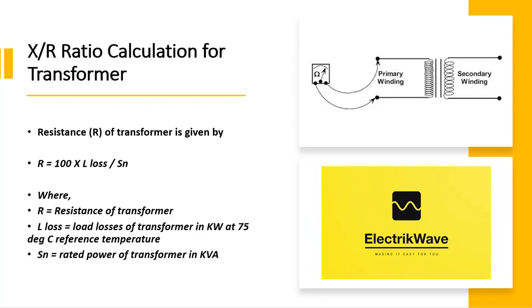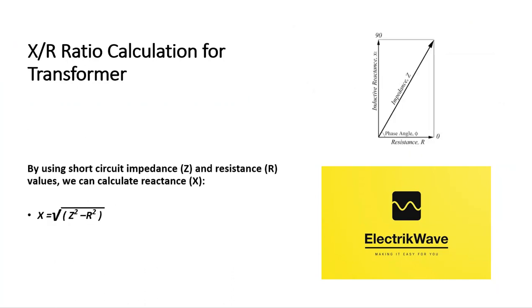Resistance R of the transformer is given by the formula, where R equals resistance of transformer, L_loss equals load losses of transformer in kW at 75 degrees Celsius reference temperature, and Sn equals rated power of transformer in kVA. By using short circuit impedance Z and resistance R values, we can calculate reactance X as shown.